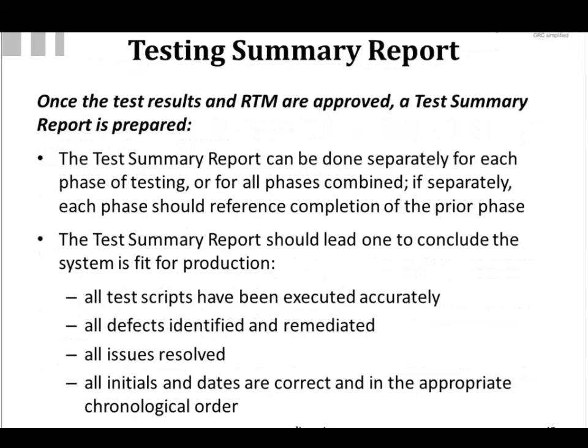Now, once the RTM is approved, then you're going to have a test summary report. The summary report can be done, again, separately for each phase or one for all three phases combined. If it's separately, then each phase should reference completion of the prior phase.